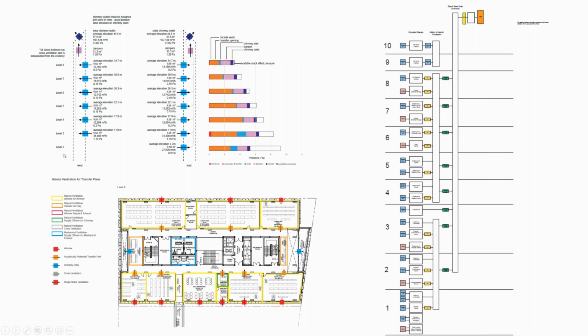And in this building, we actually have a lot of interconnections from the atrium and the lower floors, as well as different stairways, which are really great for the system being really active. But you have to be conscious that air will flow through the path of least resistance wherever. So we have a network airflow model to make sure that the air isn't short-circuiting any particular zone, and that all the zones will achieve their target airflows, both for ventilation and for cooling.